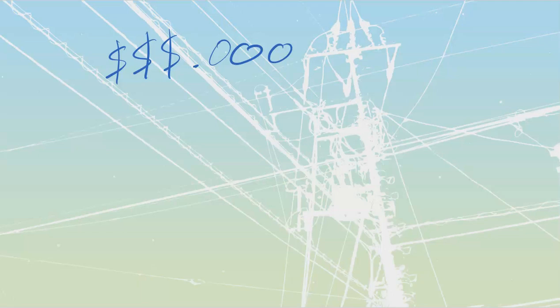In the cases of very large variable frequency drives or adjustable speed drives, those things can be up into the tens, if not hundreds of thousands of dollars. Which means that if you, as some hairy electrician out there, just go and scab that thing together and then turn it on, you can blow up some big money pretty quickly. And so in a lot of cases, the wholesalers will actually go and send out a tech. If you've been installing an ABB drive, they will have the ABB representative come out there to do the commissioning.